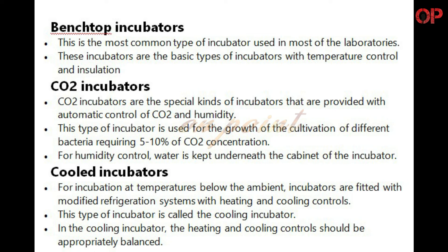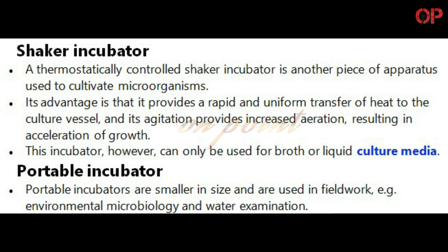Cooled Incubators: For incubation at temperatures below the ambient, incubators are fitted with modified refrigeration systems with heating and cooling controls. This type of incubator is called the cooling incubator. In the cooling incubator, the heating and cooling controls should be appropriately balanced. Shaker Incubator: A thermostatically controlled shaker incubator is another apparatus used to cultivate microorganisms. Its advantage is that it provides a rapid and uniform transfer of heat to the culture vessel, and its agitation provides increased aeration resulting in acceleration of growth. However, it can only be used for broth or liquid culture media.